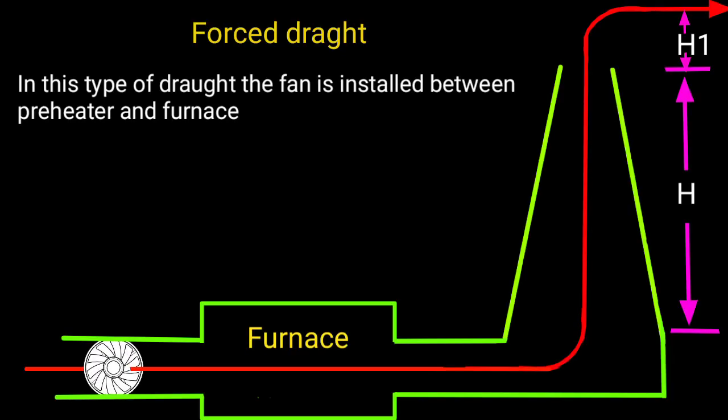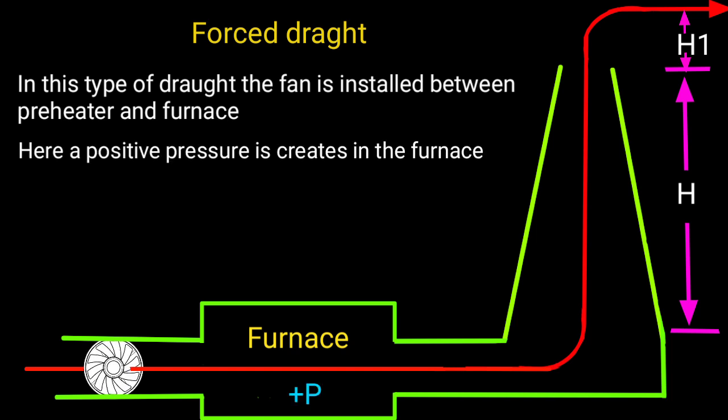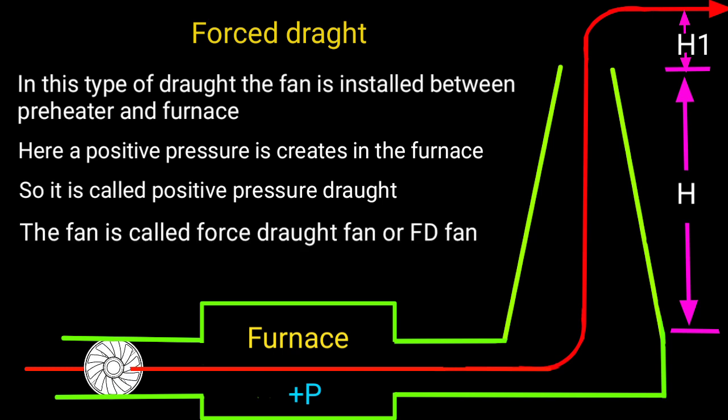Force draught. In this type of draught, the fan is installed between preheater and furnace. Here, a positive pressure is created in the furnace, so it is called positive pressure draught. The fan is called force draught fan or FD fan.